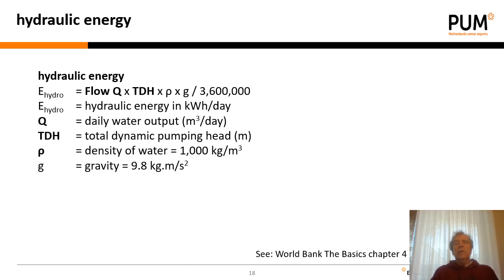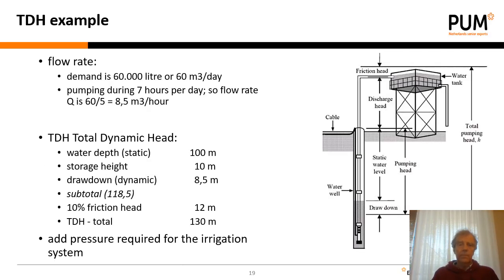So here we put out the different parameters that we need when we calculate the hydraulic energy. So let's do a TDH example. Suppose we have a demand of 60,000 liters or 60 cubic meters per day, and say that we are able to pump during 7 hours per day. So the flow rate is 60 divided by 7, which is 8.5 cubic meters per hour.